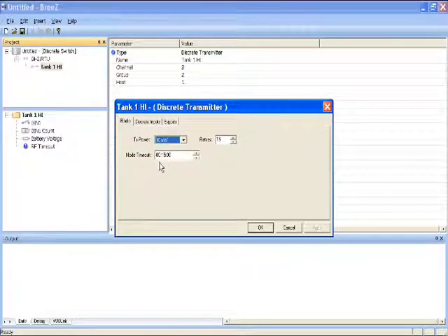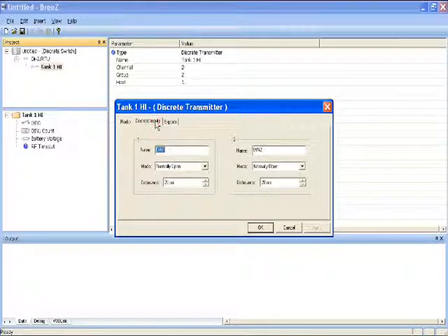The node timeout is an RF flag in a Modbus register that signifies to the DH2 if data has not been received within this time setting. Leave this at default of 15 minutes. The discrete transmitter is a cry-out device, but does send a health packet every 5 minutes. Leave retries at 15.